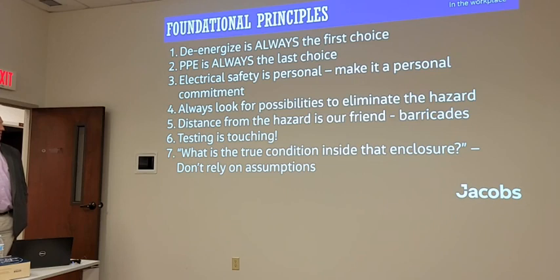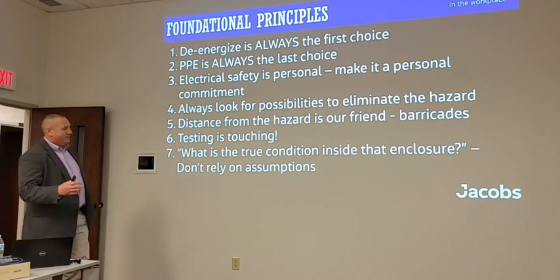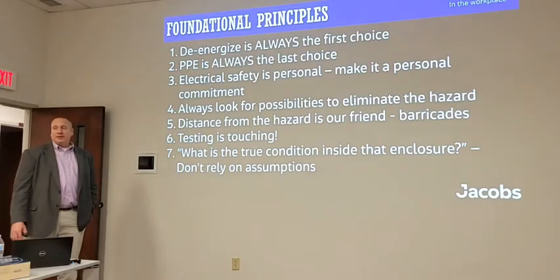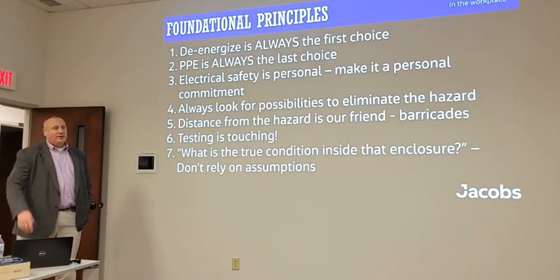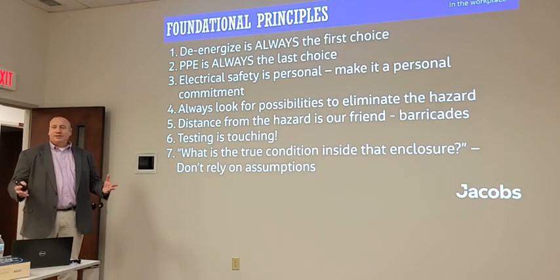Then ask yourself, what is the true condition inside that enclosure? Don't rely on assumptions. And also be aware of what you're exposed to, not just what you're working on, because oftentimes there's multiple voltage classes in enclosures, and you may be working on something that's controls level voltage, but it also may have some supply power inside that enclosure that causes you to be inside that arc flash boundary.